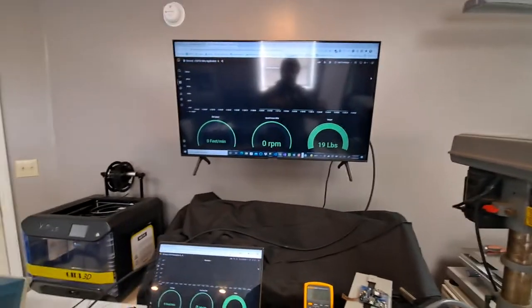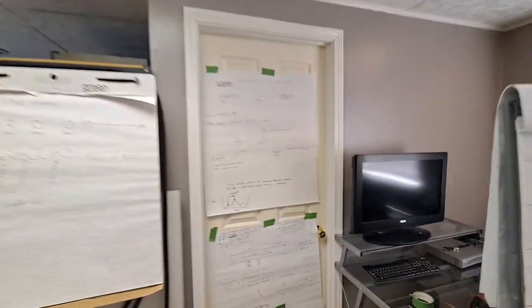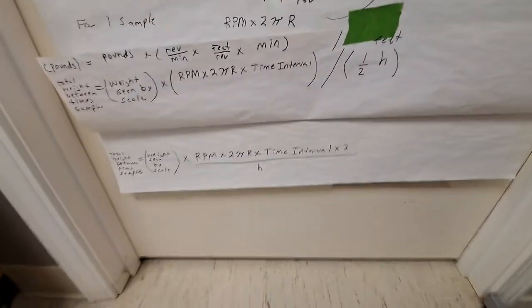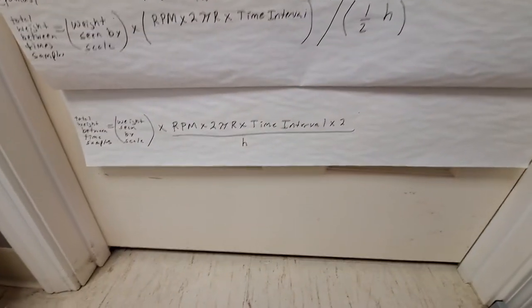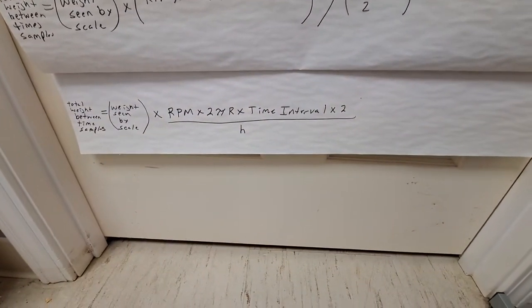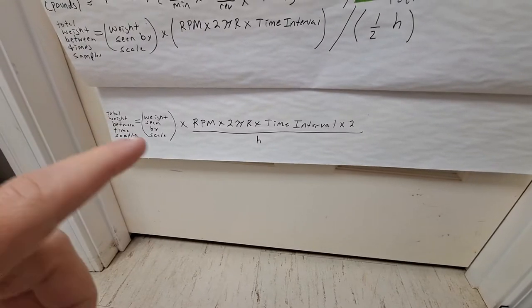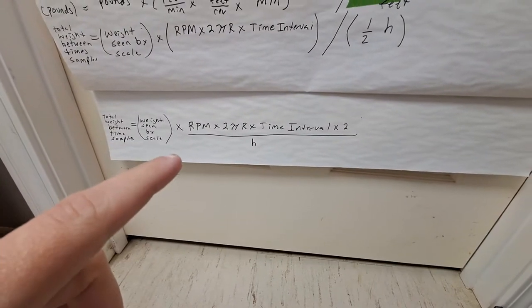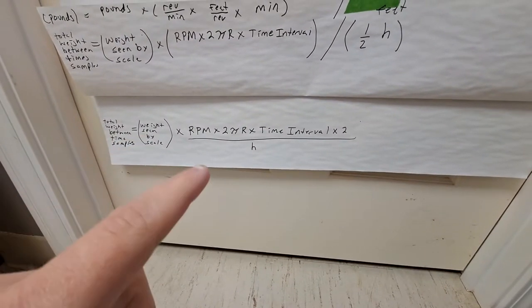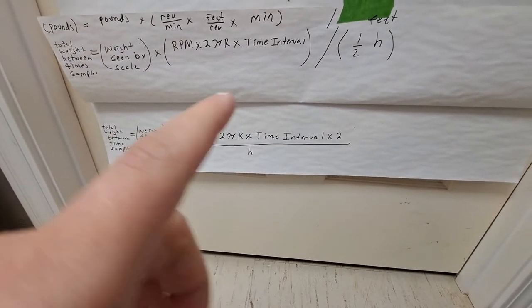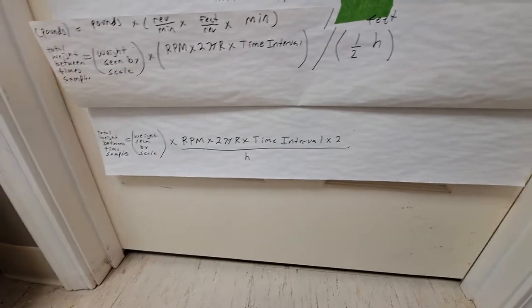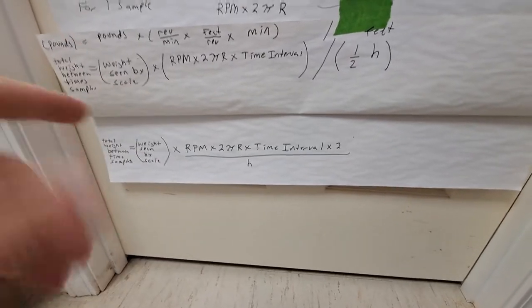The other piece is how fast the belt is moving. And we did a little bit of math here. And we have this equation right there. Basically, we have RPM, time interval, and H, which is the distance between the idlers.